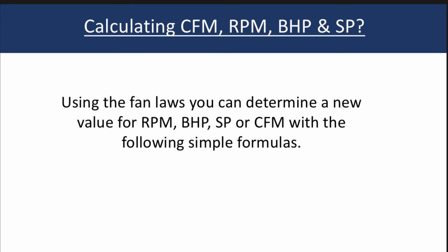We can calculate RPM, brake horsepower, static pressure, or CFM with the following formulas. But before that, I want to show you again how these numbers change. If you know three of these values, you can determine the fourth. It's just a basic math formula. So if you're looking for a new condition on an existing fan, you can determine that by getting the values from the existing fan.